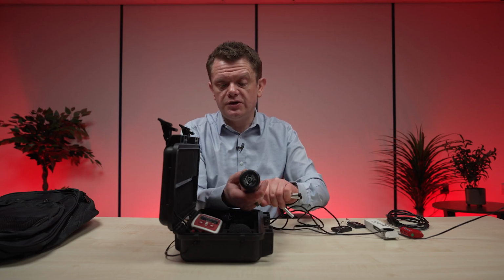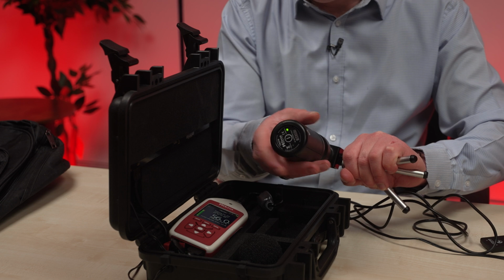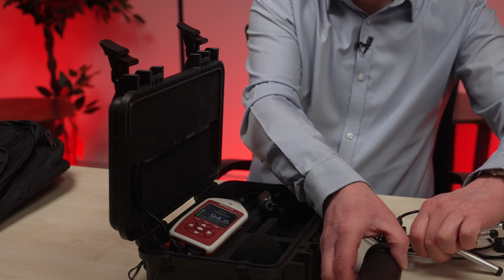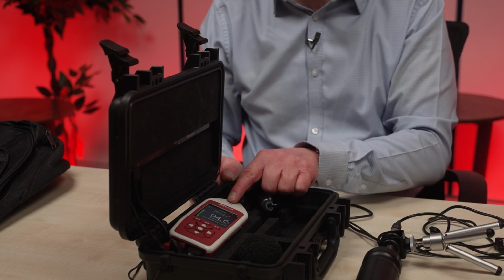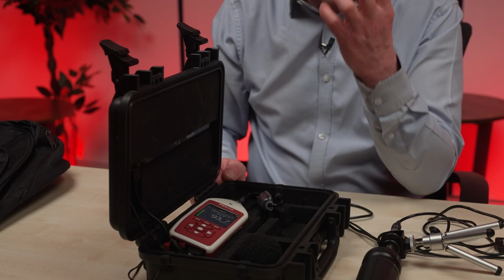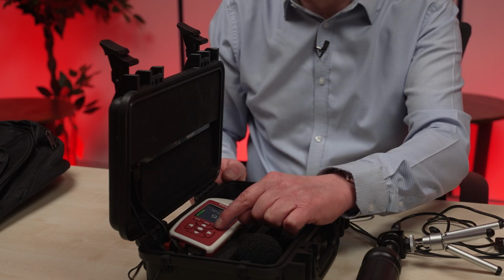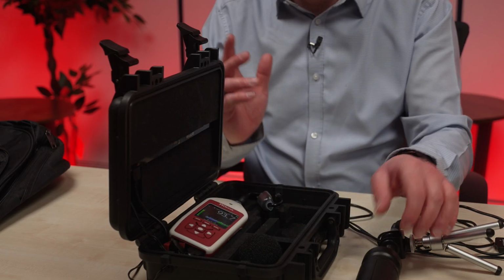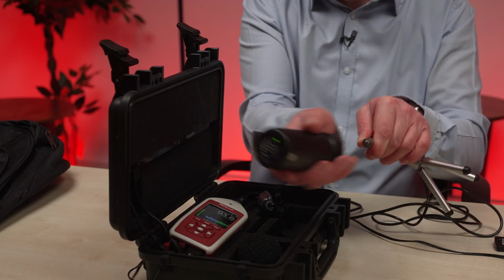Place the calibrator on top, press that button again, one time, and you can see on the screen it's waiting for a calibration tone that it's happy with. It's accepted that level, so I just have to press the button underneath the word OK. And then from that point, it's simply a case of...